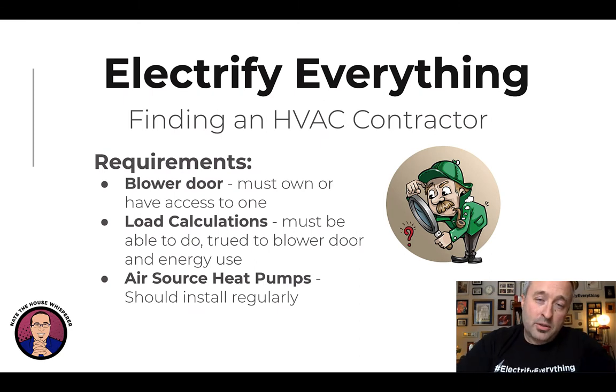To find an HVAC contractor, there are three things they need to be up to speed with. First, they need to have a blower door, and that's going to shrink the pool a lot—this is going to be a couple percent of contractors. They need to be able to do load calculations, which again is going to shrink the pool a lot. Lots of contractors will say they do load calculations. You need to ask to see some and ask what program they use, because hopefully they're not doing it on paper. And they also need to true that load calculation to both blower door and energy use, and only a few programs are really good at doing that. So these are important pieces of the puzzle.